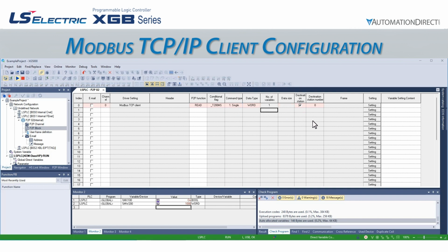Destination station is LS nomenclature for node address. This is the unique identifier for a specific serial node on a Modbus network. For Modbus TCP servers with a unique IP address, this can be any number. The GS20's communication card, however, is a Modbus gateway that has a node address for its drive data at node 1 and a node address for the drive's internal PLC at node 2. We will have to set the destination station to 1 since we want to read from and write to the drive data.